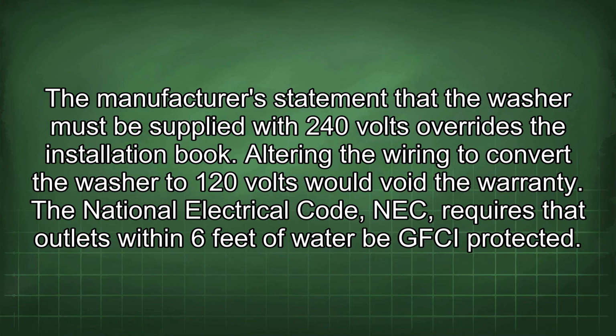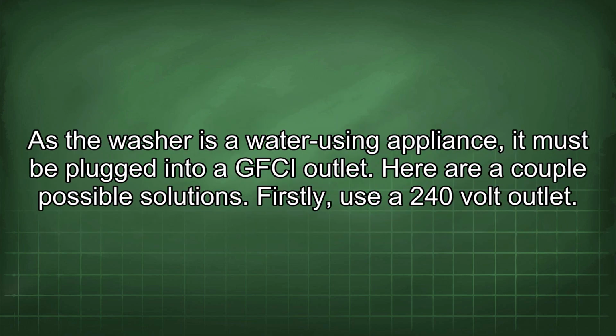The manufacturer's statement that the washer must be supplied with 240 volts overrides the installation book. Altering the wiring to convert the washer to 120 volts would void the warranty. The National Electrical Code (NEC) requires that outlets within 6 feet of water be GFCI protected. As a washer is a water-using appliance, it must be plugged into a GFCI outlet.